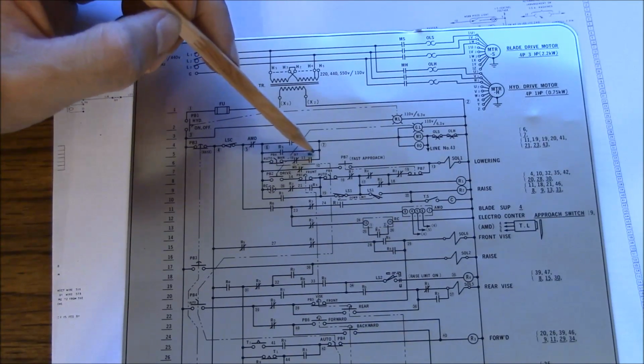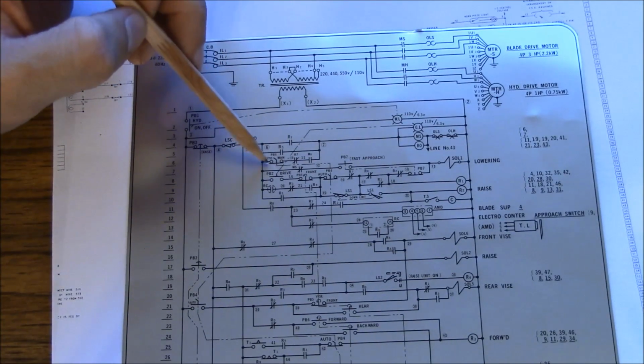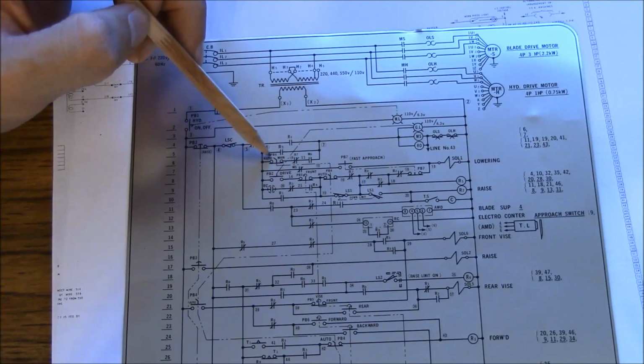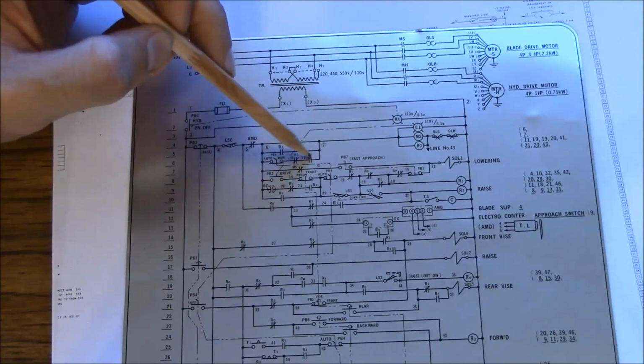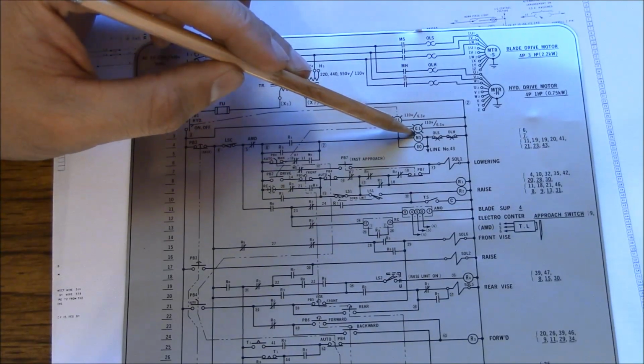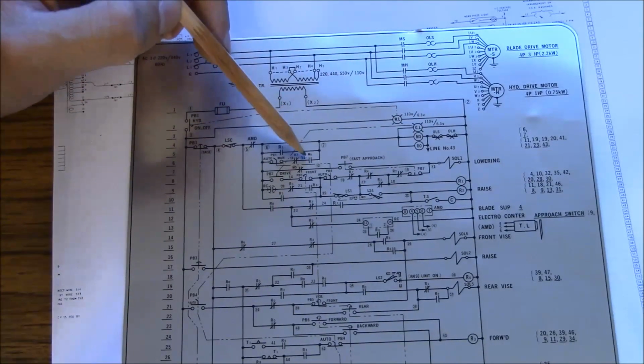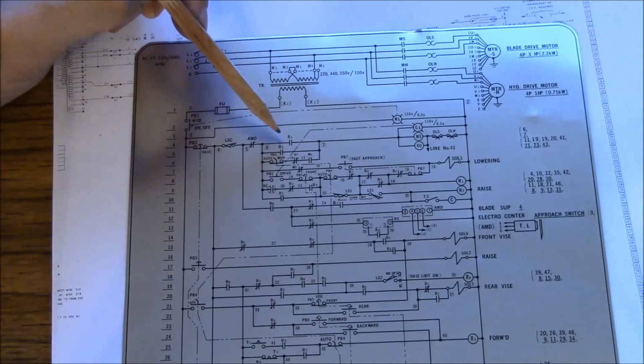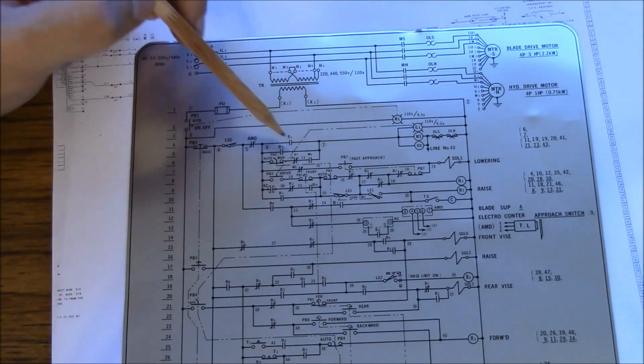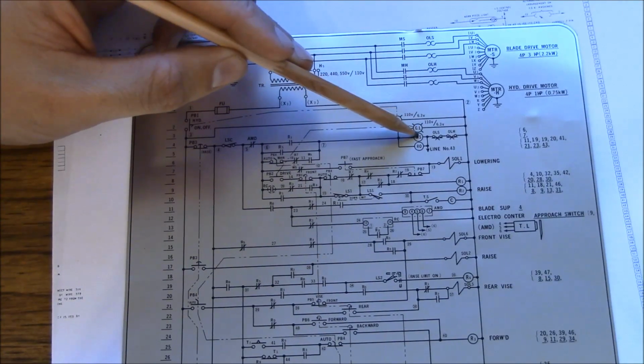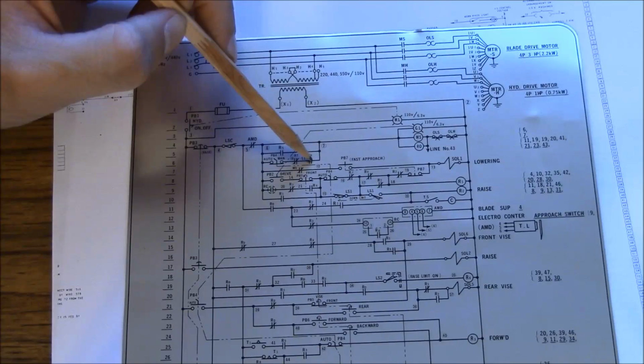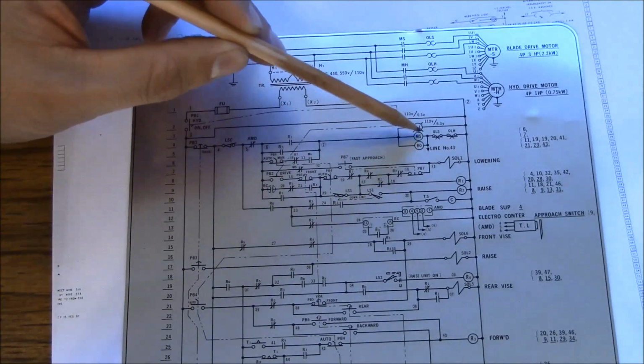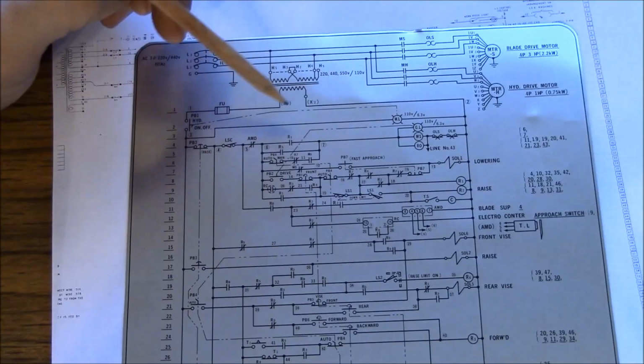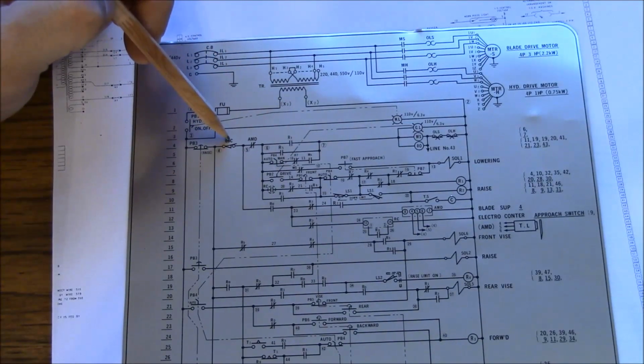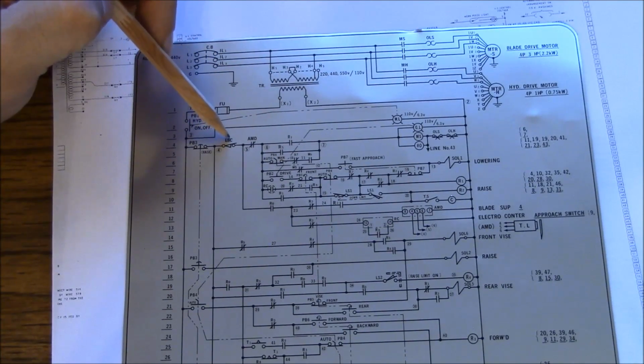that's basically the latching relay. So I guess if you're in the auto mode or manual mode, this is how the circuit can latch itself and hold the MS coil in. So that's exactly like the example that I showed. So probably what happens is you push a button and R1 comes on. It turns on the MS coil. The MS coil closes and latches itself, and then basically the motor is going to stay on until this limit switch gets made. That's probably the bottom of the blade travel limit switch.